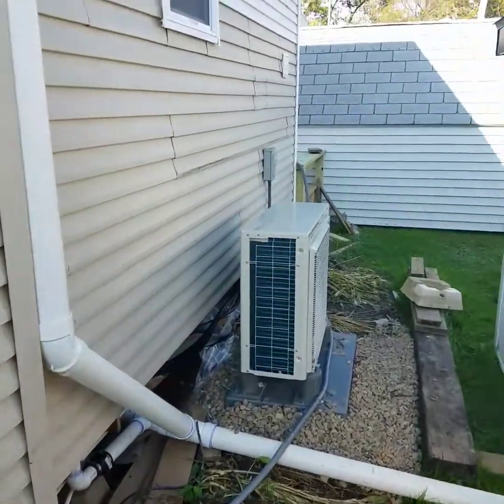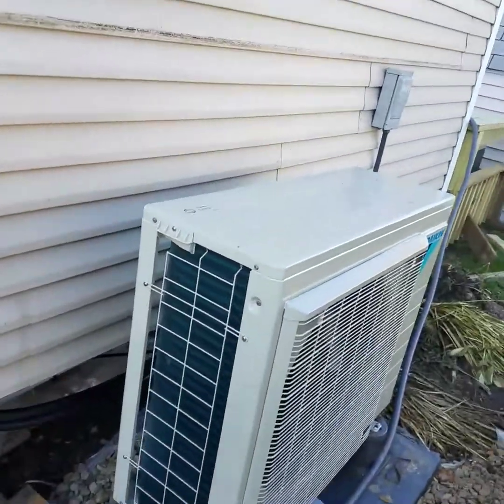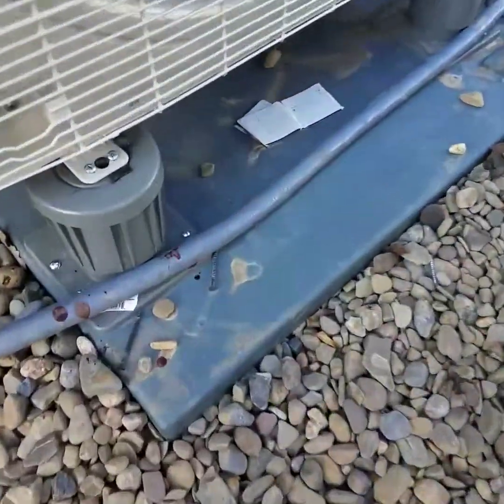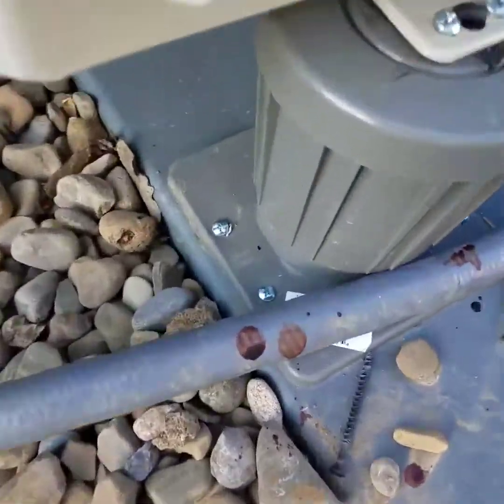Here's the unit. These guys have been out here five times already. Originally, they took drywall screws and fastened the unit in with drywall screws — and here they are, all over the place. They just left them. This unit here was not on level. They came out and put zinc screws in — see that? That's zinc, you can just tell by the sheen. That's stainless steel. Zinc. Stainless.